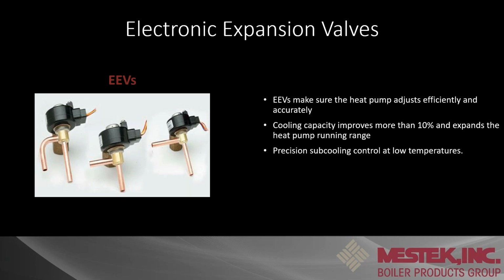So this will improve your capacities by 10%, because again, we're trying to match exactly what the refrigerant is doing and how much we're going to let go out to our coil. On top of that, it gives you precision subcooling control at low temperature. It's going to self-adjust to make sure we have proper subcooling the whole time it's running.